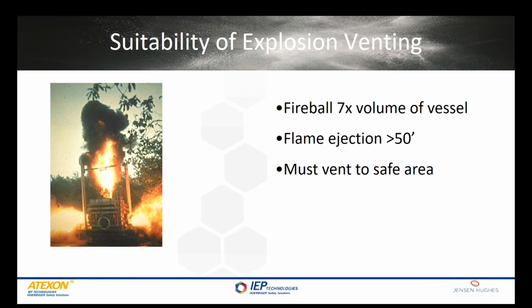So when you're trying to determine whether or not explosion venting is a suitable protection option for your facility, it's very important to ask: do I have a clear path for that flame to be ejected, where you're not going to have people, a sidewalk, or other parts of the building that could become ignited, other process vessels and so forth? It's very critical that that be considered when determining if explosion venting is the right explosion protection technique for your application.